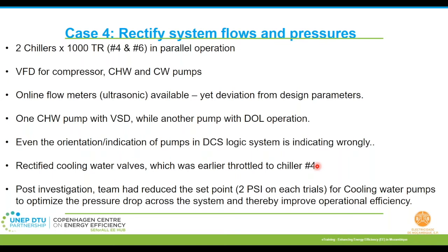We need to apply logic, because there were certain places where the control system was showing that the valves were open, but in reality, when we measured the flows, we found that there was some throttling happening and there were pressure imbalances. So through physical measurements, we had to tune the control systems first, and then ensure that there is sufficient water going to the chillers and other air conditioning systems to improve the overall operational efficiency.